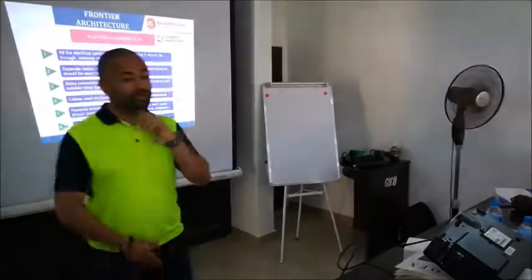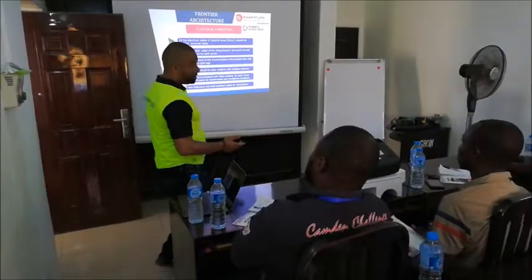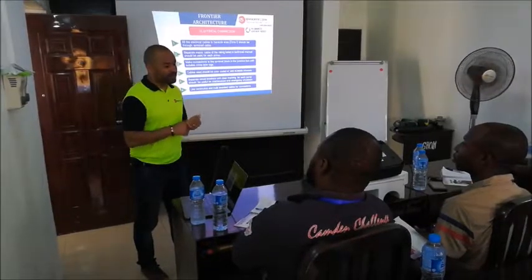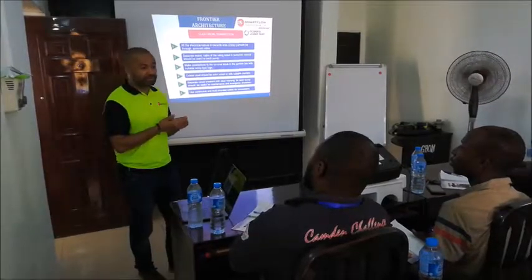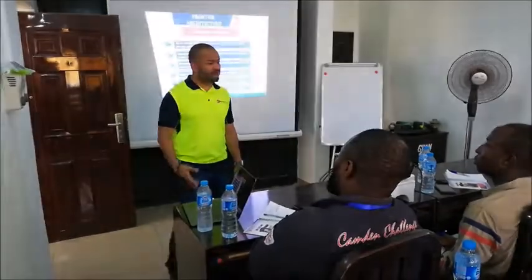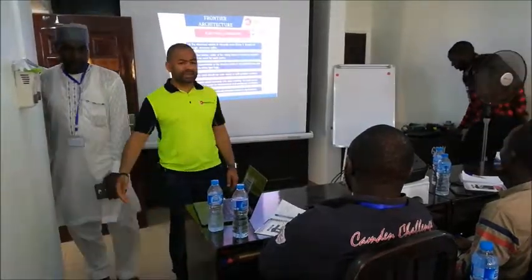This is the recommendation. Some people will take one cable and run it inside, but we prefer that when you are connecting in the junction box, instead of using bare wire, you use a lug or crimps. Your cable should also be color coded — you cannot be using yellow for live and brown for ground or earth.